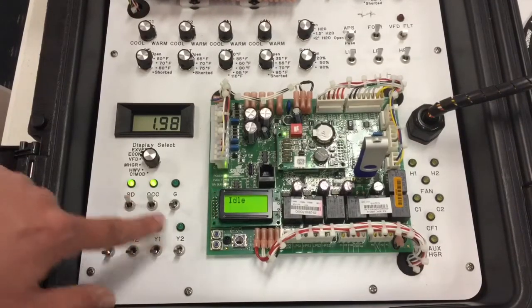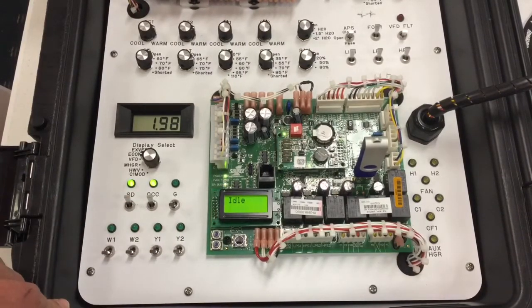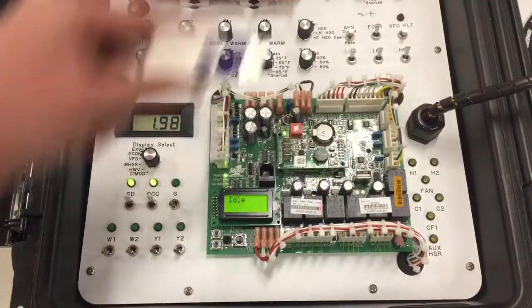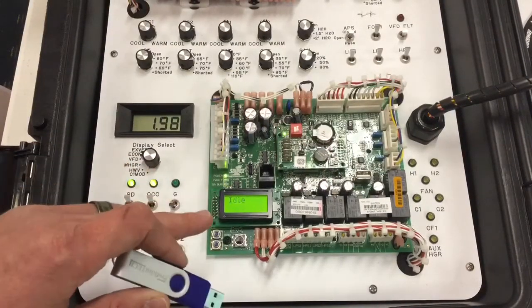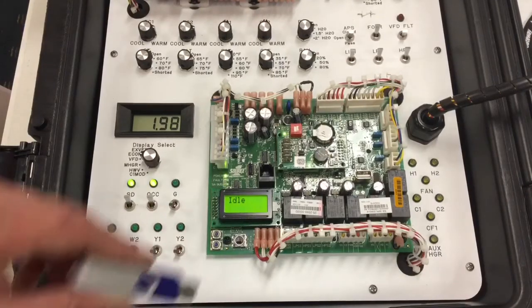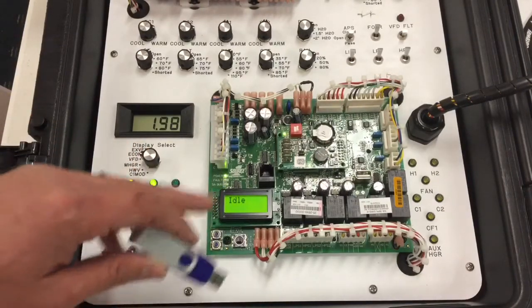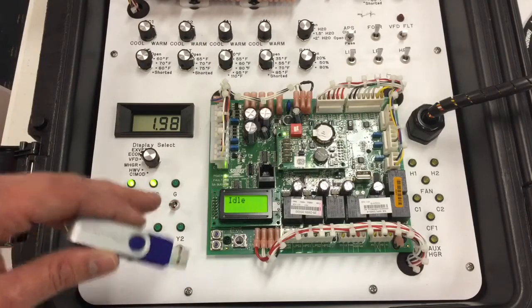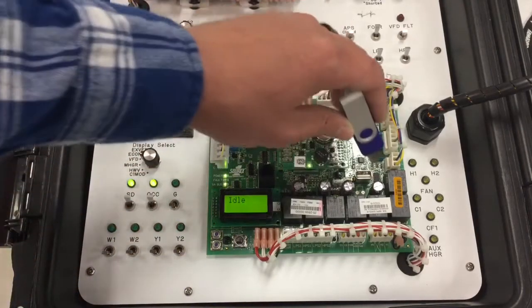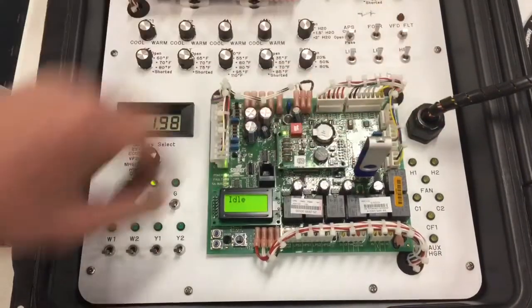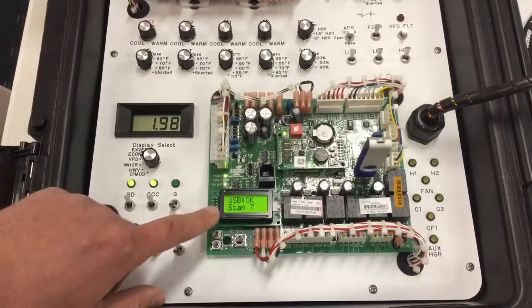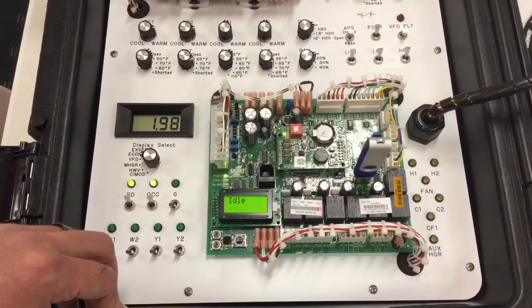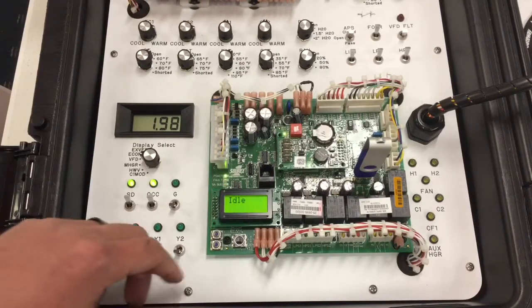I have no calls for heating, no calls for cooling. I'm going to remove my flash drive and I'm going to place my flash drive back into the control board to make sure that I've successfully created a backup file. Earlier it said backup USB OK 6. When I place the flash drive back into the control board, it should increase by one number. Scan 7. So I know I've successfully done a backup on this system.